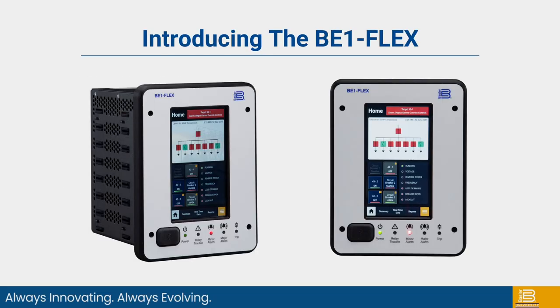The BE1-FLEX comes with a 7-inch touchscreen display. The display one-line diagram is configurable. Tools such as Inkscape can be used to make a one-line diagram that matches your specific application. The control push buttons can be used to operate breakers or other items, such as a maintenance mode switch to enable a lower arc flash energy setting, enabling an instantaneous element with a lower setting to trip the breaker faster when personnel are working on the breaker.